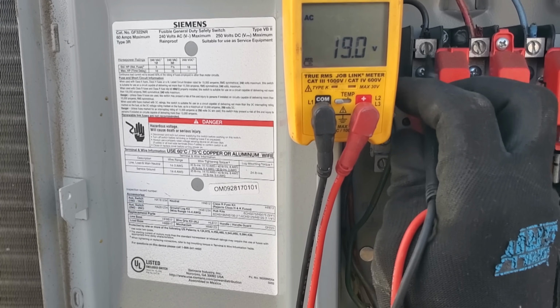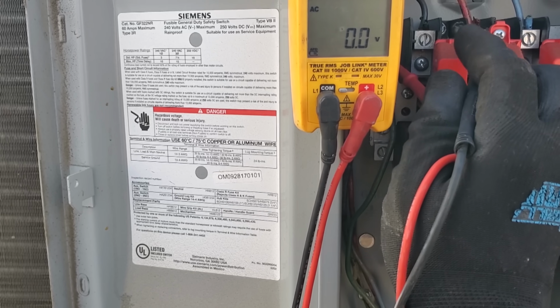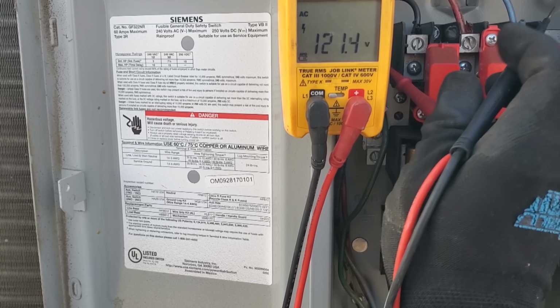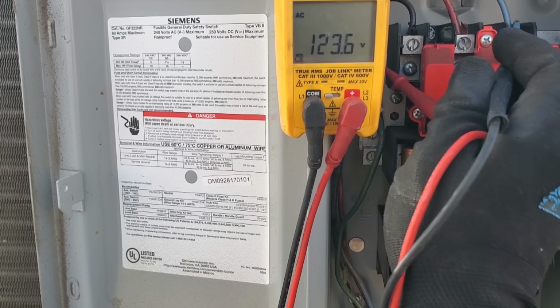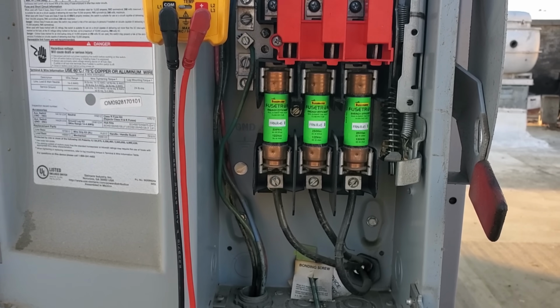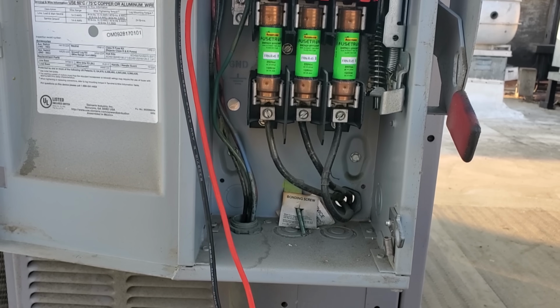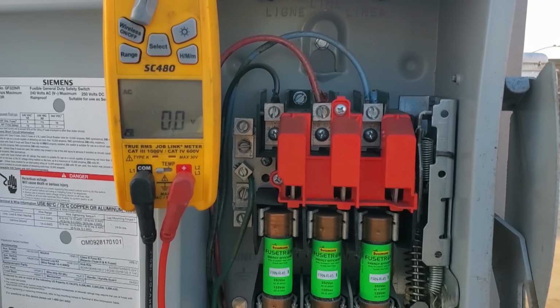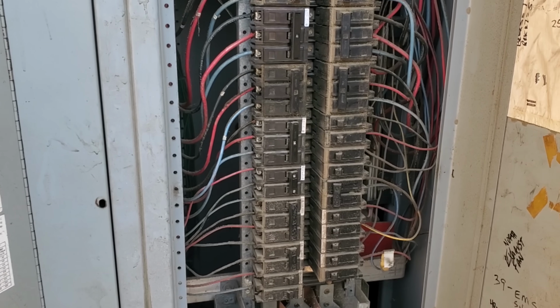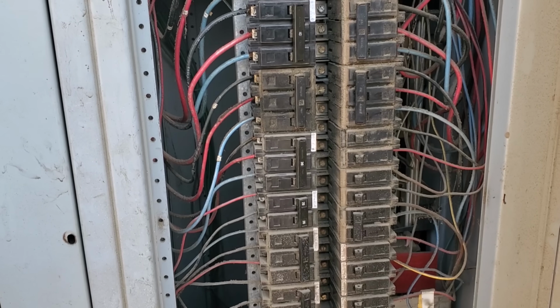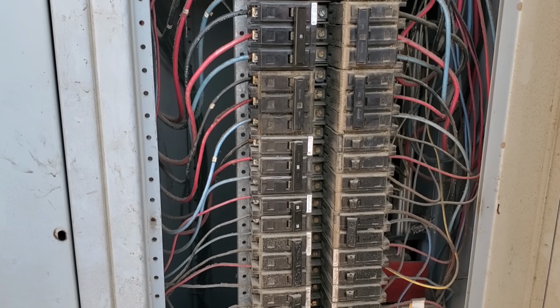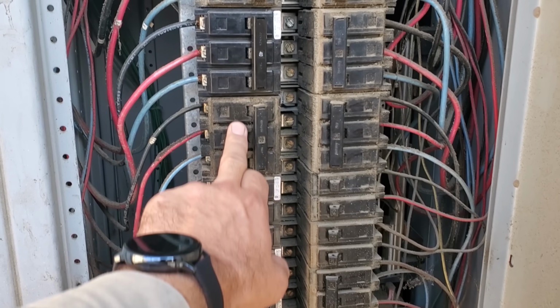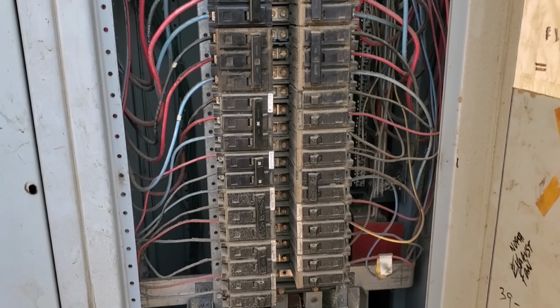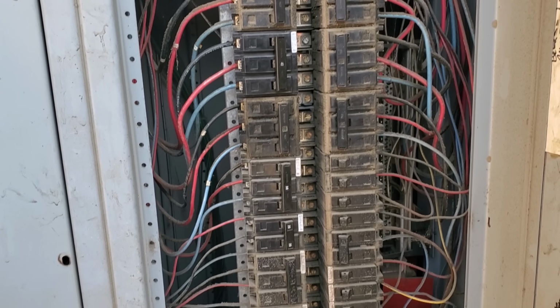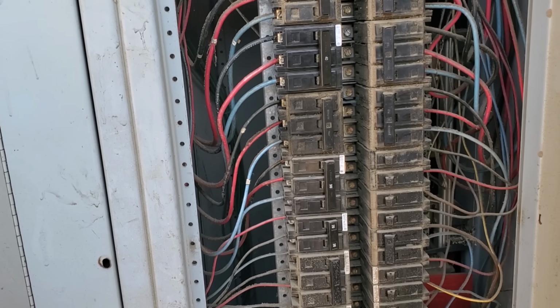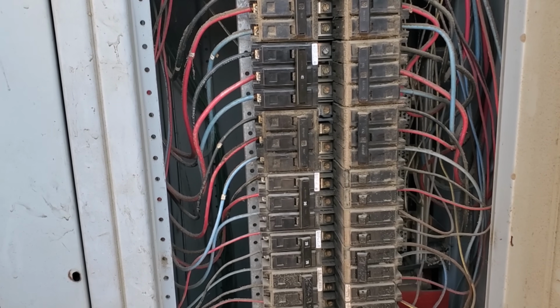19 volts to ground. That is a trip. Keep going over. 120, 120. There's something funky going on here. All right, we need to go downstairs to the breaker panel and see what's going on down there. All right, this labeling could be all messed up, but I believe that this is our breaker right here. So we're gonna go ahead and test it. It's not tripped. There's nothing tripped in the panel. It's certainly messy, but I've seen worse. So we're gonna test voltage at the breaker and see if that's where the issue's at.